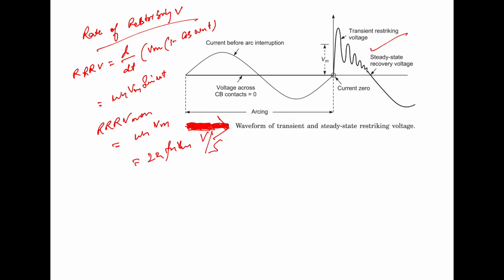This occurs at the time of pi divided by 2 omega n. Since the natural frequency of the system is given by 1 by 2 pi root LC, it can easily be in the kilohertz range. The value of this RRRV max can indeed be very large for high voltage power systems. So now the question arises: can we somehow manage the switching within the circuit breaker in such a way that the restriking voltage is reduced? So we can discuss that now.